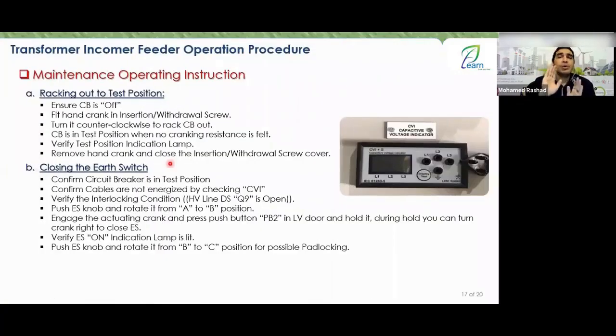Now, if you want to perform maintenance, I will open the breaker, open the insertion hole, insert the handle, perform a rack out, and the breaker is now racked out. I check the breaker above, it's racked out, remove my handle, and finished with the breaker. I hold the grounding switch, wanting to close the grounding. I ensure the breaker is open.